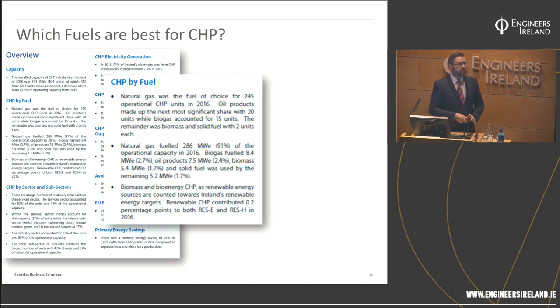CHP needs to run 24/7, and it can run 24/7 for maximum efficiency and maximum output if you've got a clean, reliable supply of gas - that's key. Unfortunately it's hard to do that with a lot of other fuels, but when those fuels are available, we're always available to convert CHPs to run like that. So in parts of the country where they don't have gas, we have a lot of LPG units - down in Kerry is one area we have a lot installed. You probably know more about it than I do, but that allows a completely off-the-grid setup.